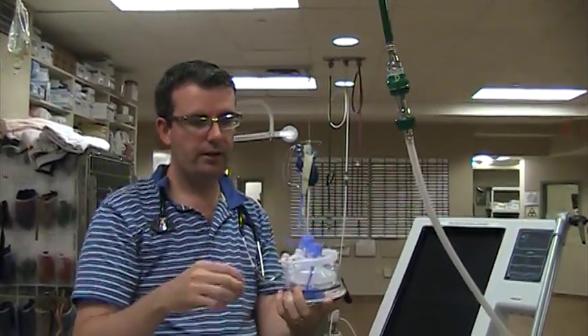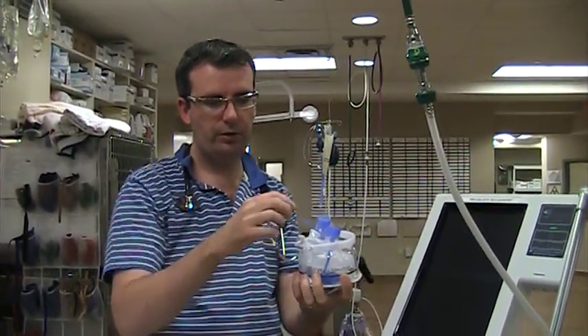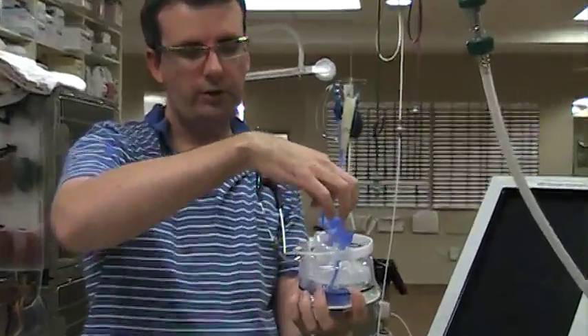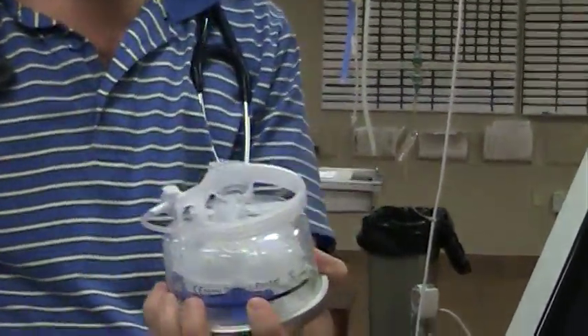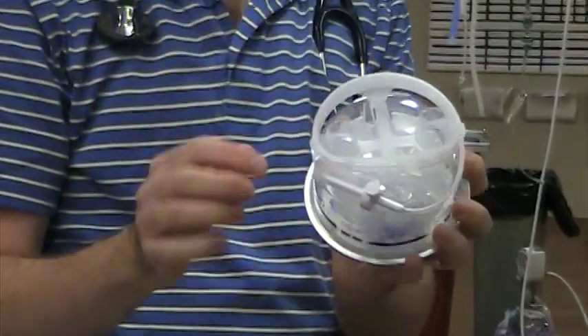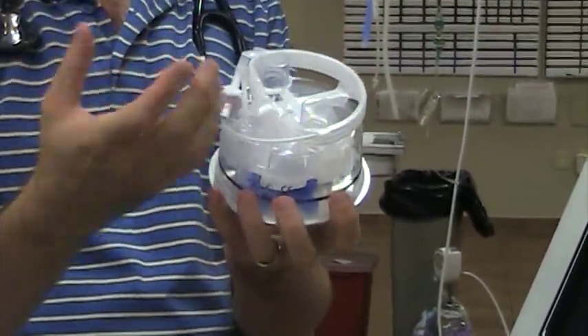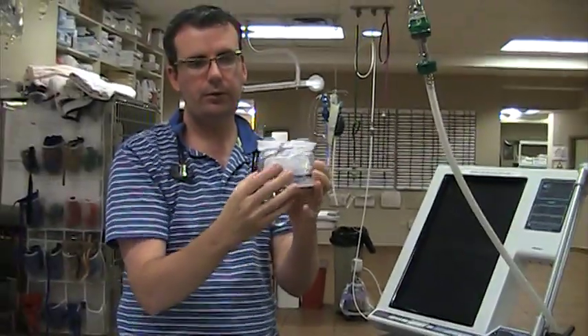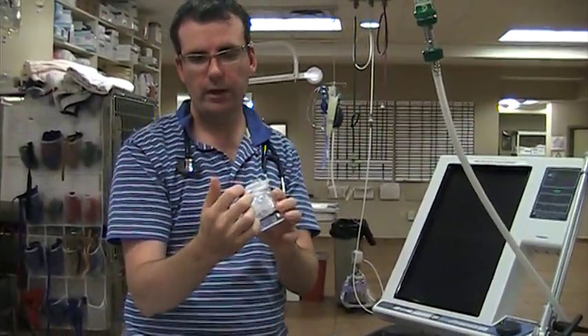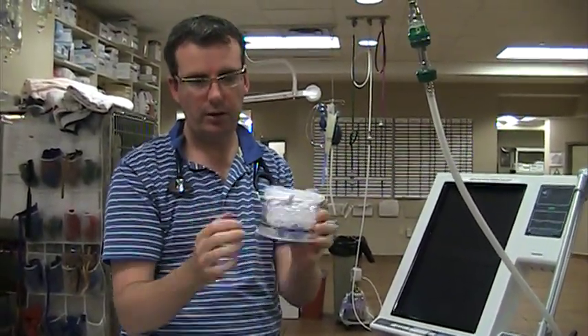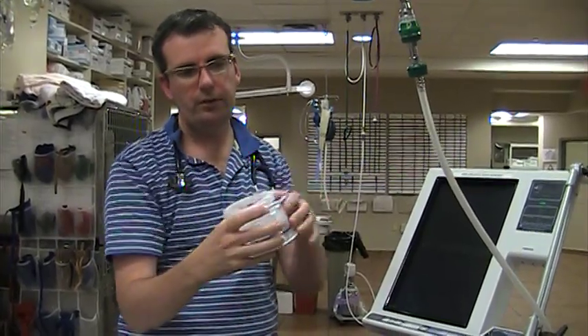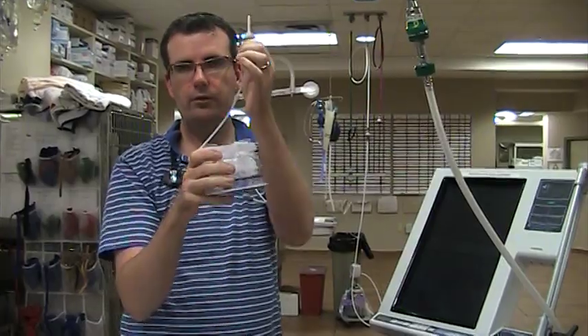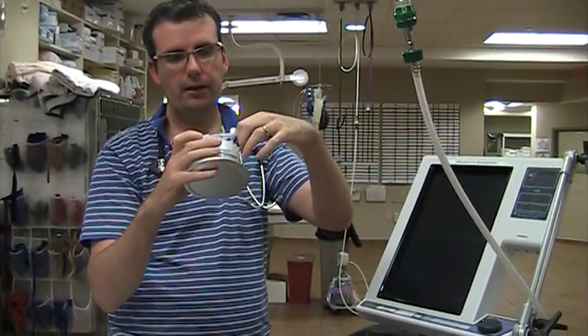So basically to set it up, have the technician fill it with the distilled water. To do that you just have to pull this out, and then they can put the distilled water in there. This is tubing that connects to the water bag so that this automatically fills, but we leave this the way it is at this particular point in time. So still fill it with water, but leave this in. Basically what happens is that spike goes into the distilled water bag once we've set up the ventilator.